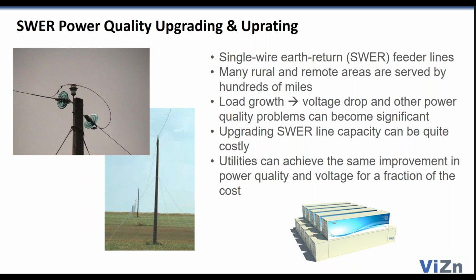So you have a choice: go back and upgrade, hang a second line on these to increase capacity, and there's a cost to that. What we're seeing is that utilities can achieve the same improvement in power quality and voltage for a fraction of the cost, depending on the length and age of the line. So this isn't the sexiest of applications, but it's one where an energy storage system can come in at a fraction of the cost of the alternative.